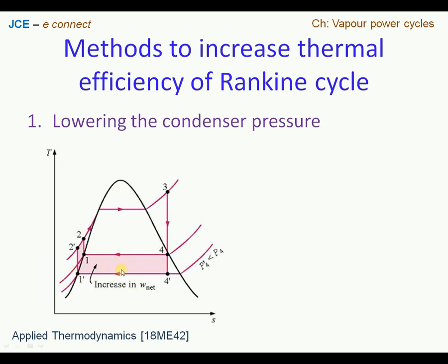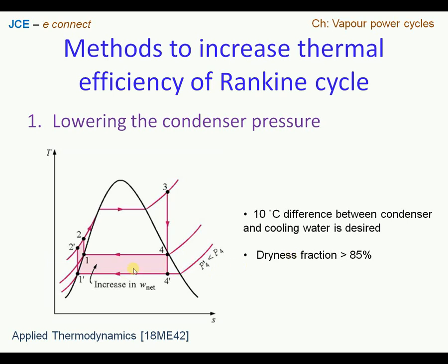But here is a constraint, that one cannot go on lowering the condenser pressure, because this is dictated by atmospheric conditions. If it is well below the atmospheric conditions, then a vacuum can set up, and there may be bubble formation and so on.